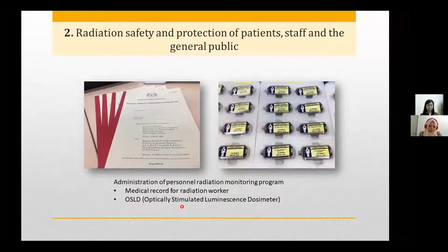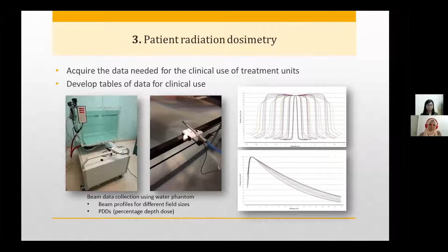So medical physicists will acquire the data needed for clinical use of treatment units and develop tables of data for clinical use. So this is what we have done for every LINAC machine installed. So beam data collection using water phantom. Then we scan for the beam profiles for different field sizes and also the percentage depth dose for different field sizes as well.